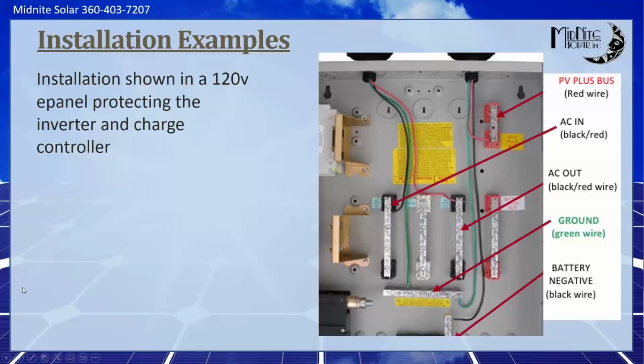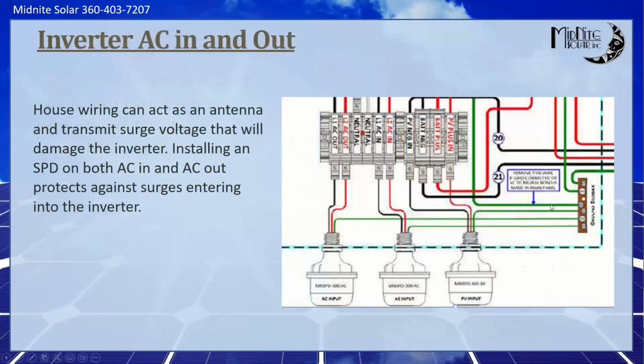And I got a question about the Rosie E panel and a second SPD for the neutral. Generally speaking, no, because the Rosie E panel is either going to have your neutral to ground bond in it if you're off grid, or it's going to be so close to the main panel that the bond is sufficient to cover the neutral in the Rosie E panel. So the Rosie E panels ship with a neutral to ground bond internally, and if you're using them in a grid connected environment, you remove that bond. So I would say, generally speaking, no. If you've got a use case where the Rosie is a couple 100 feet away from the main panel and the bond is in the main panel, then you might want to think about it, yes. Yep.